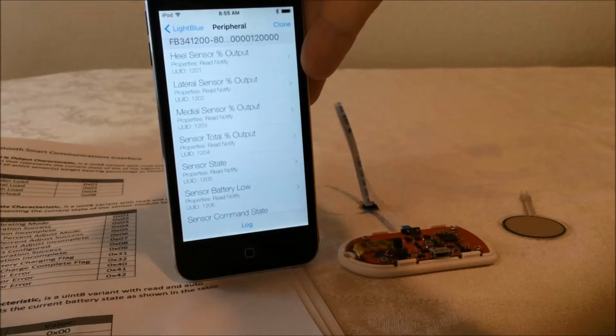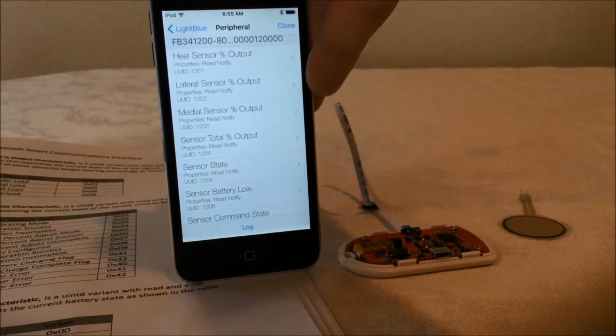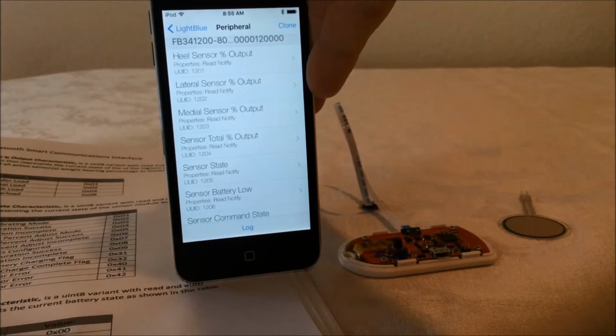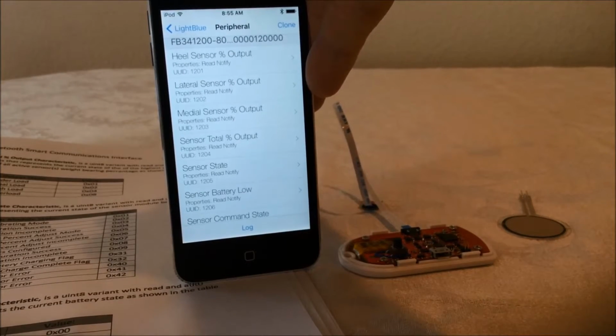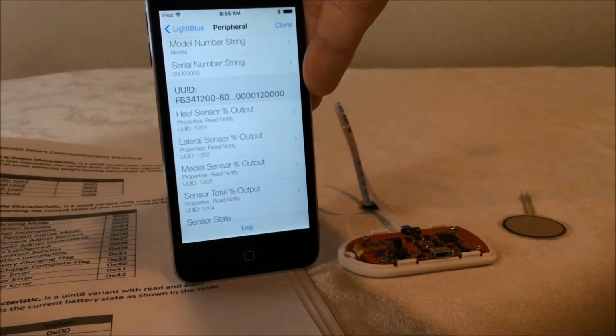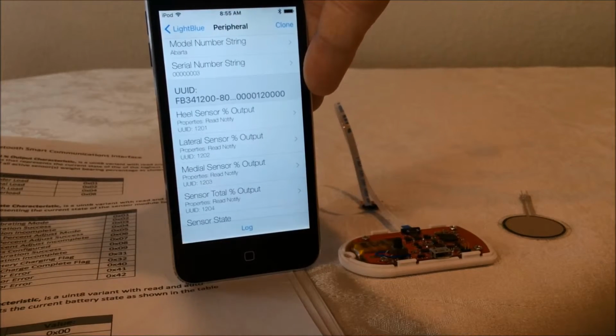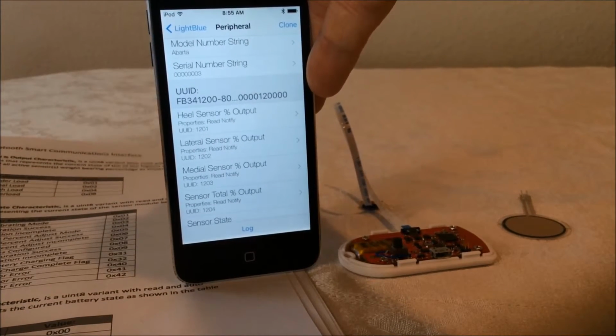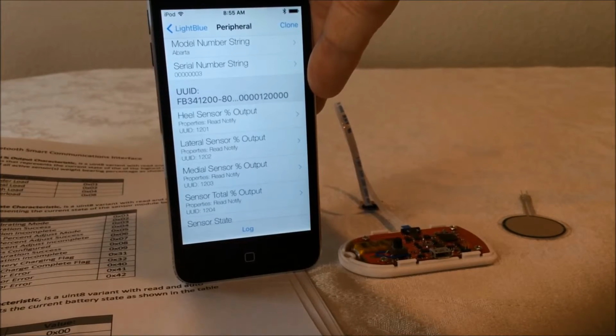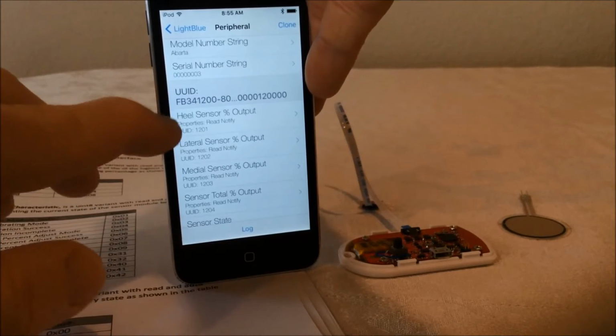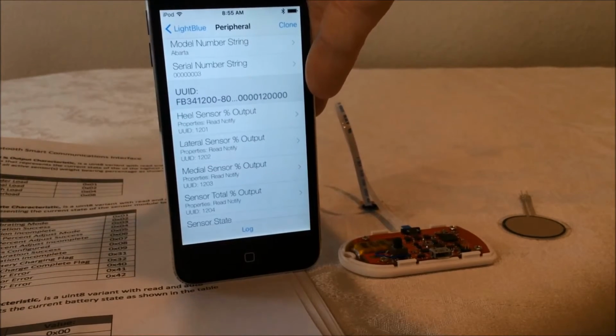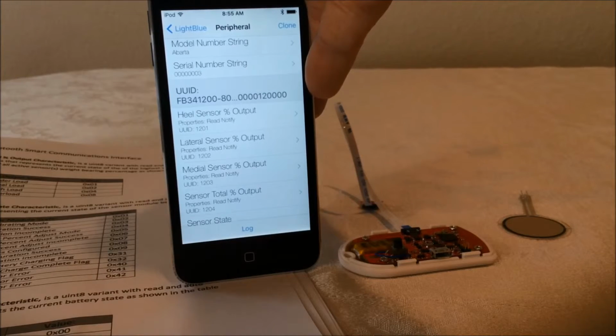This makes the application really cool, because after you go through the sensor setup and calibration stages, in runtime mode these are live updates. So whenever you're pressing on the sensors — weight bearing load on the heel, lateral, or medial sensors — you'll get a percentage output equating to the current weight bearing output you've set up.